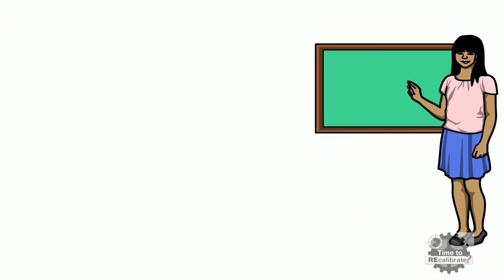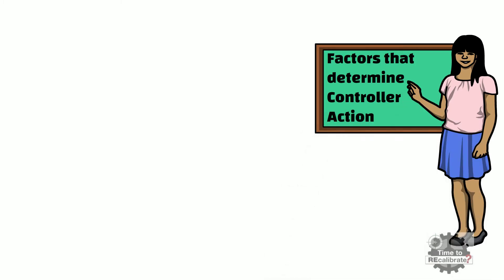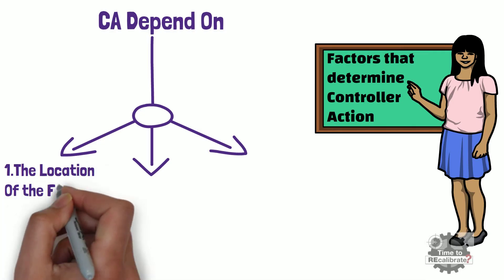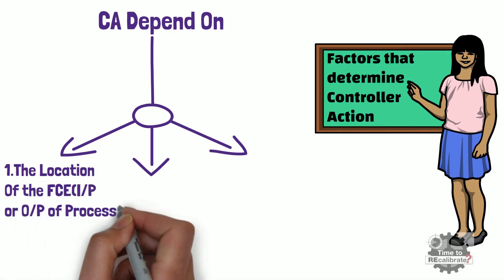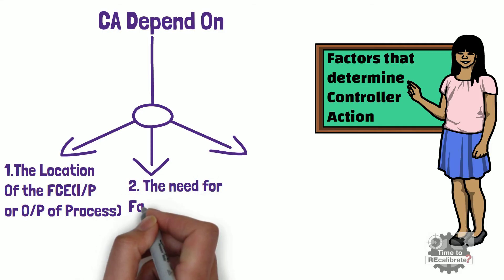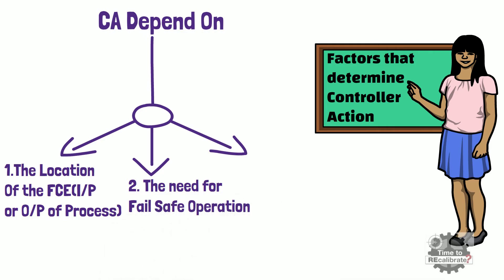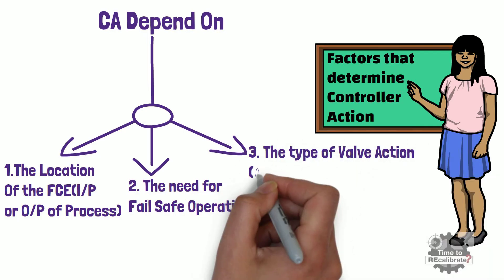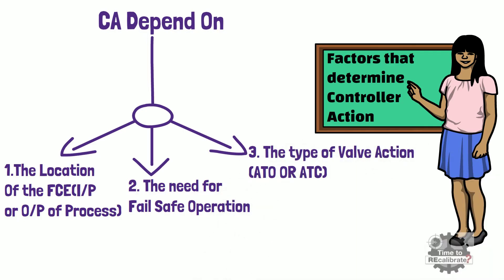Now let's learn about the factors that determine controller action. First, controller action depends on the location of the final control element — specifically, whether the flow control valve is located at the input side of the process or at the output side. Secondly, controller action also depends on the need for fail-safe operation. Last but not least, controller action also depends on the type of valve action — for example, whether the valve is air-to-open or air-to-close.